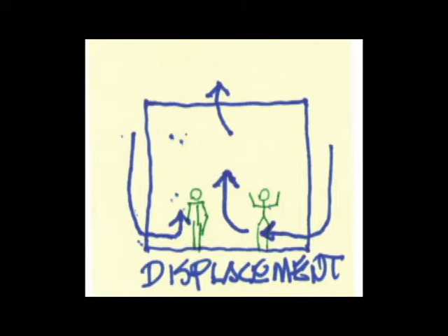The way displacement air conditioning works is, imagine an aquarium, a fish tank, and imagine that the water in the fish tank is actually the air that you breathe. If you pump air in at the bottom and return it back to the pump at the top, then you're filling up the fish tank from the bottom to the top. And so if you're on the other side of the room and you sneeze in a mixed air environment, I breathe it before it returns back to the central air conditioning unit.